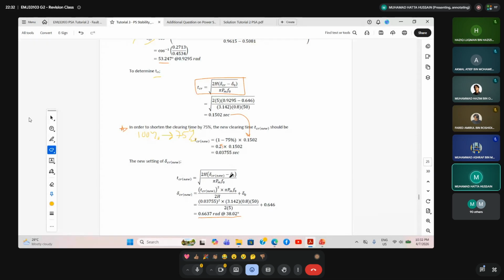And again, using this new TCR, you have to find the new setting of the critical clearing angle. By manipulating this equation, you can find the critical clearing angle, which equals 0.6637 radian, or equal to 38.02 degrees.